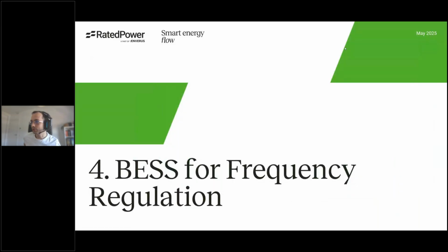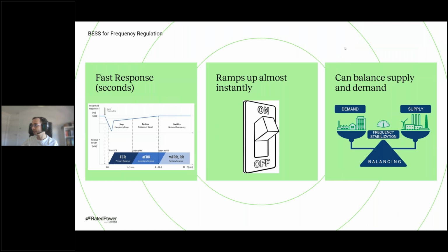So now that we know that batteries' main focus is frequency regulation, let's move on to why and how we can leverage and study this. And there are three main reasons. First, batteries are really fast, so they can jump into FCR, which is typically a more lucrative market. So very fast response. They ramp up almost instantly, so you can be at nominal power just like clicking a switch. Of course, it's not as simple, but they are very fast to ramp up to nominal power.